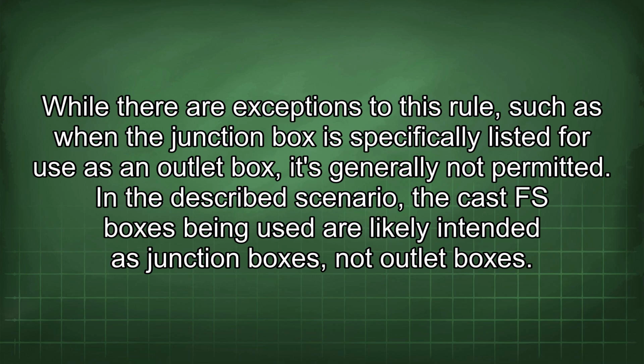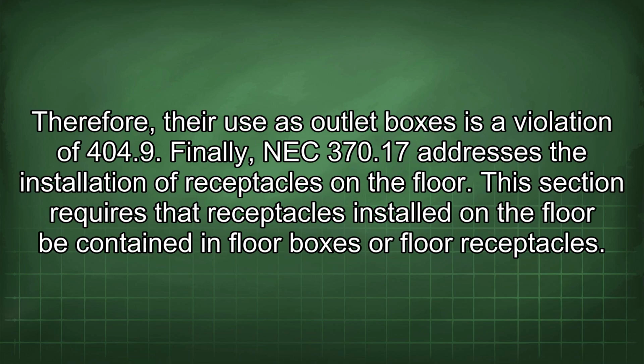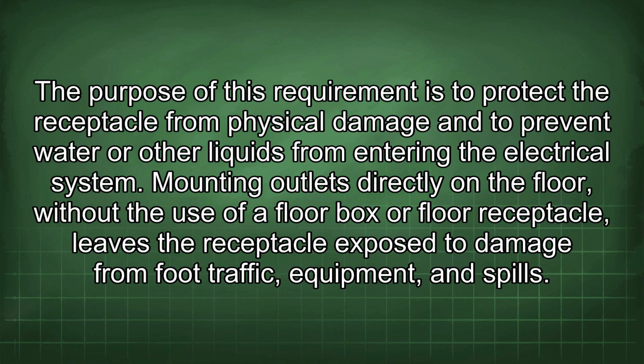In the described scenario, the cast FS boxes being used are likely intended as junction boxes, not outlet boxes. Therefore, their use as outlet boxes is a violation of 404.9. Finally, NEC 370.17 addresses the installation of receptacles on the floor. This section requires that receptacles installed on the floor be contained in floor boxes or floor receptacles. The purpose of this requirement is to protect the receptacle from physical damage and to prevent water or other liquids from entering the electrical system. Mounting outlets directly on the floor without the use of a floor box or floor receptacle leaves the receptacle exposed to damage from foot traffic, equipment, and spills.